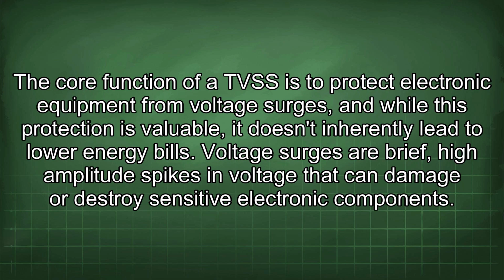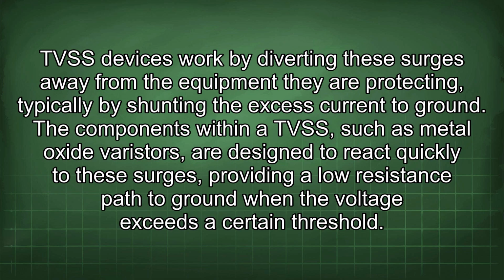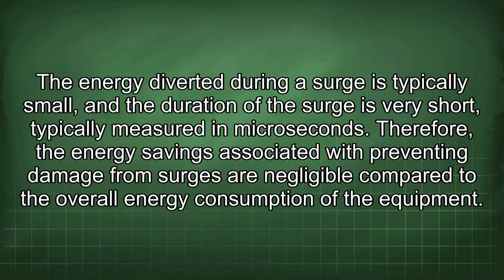Voltage surges are brief, high-amplitude spikes in voltage that can damage or destroy sensitive electronic components. TVSS devices work by diverting these surges away from the equipment they are protecting, typically by shunting the excess current to ground. The components within a TVSS, such as metal oxide varistors, are designed to react quickly to these surges, providing a low resistance path to ground when the voltage exceeds a certain threshold. The energy diverted during a surge is typically small, and the duration of the surge is very short, typically measured in microseconds. Therefore, the energy savings associated with preventing damage from surges are negligible compared to the overall energy consumption of the equipment.